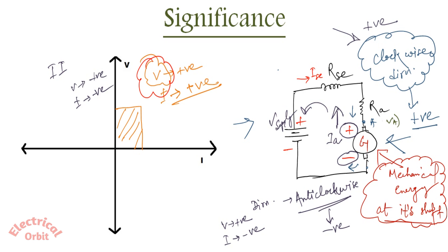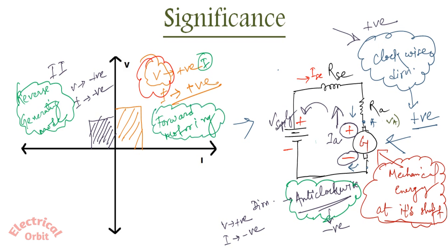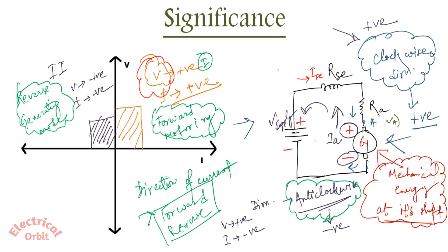Which quadrant serves this operation? This is quadrant number 2, where the voltage is positive and the current is negative. So the drive will operate at quadrant 2. We can say that as the current direction was positive at quadrant 1, that is forward motoring, and here we are getting current from the generator with the direction reversed or anti-clockwise, so this is called reverse generating mode. The direction of the current signifies whether the operation is in forward mode or reverse mode.